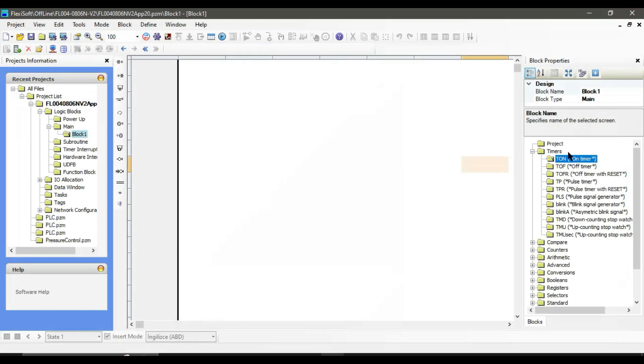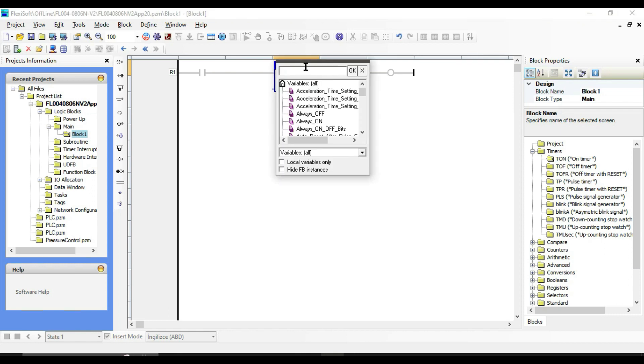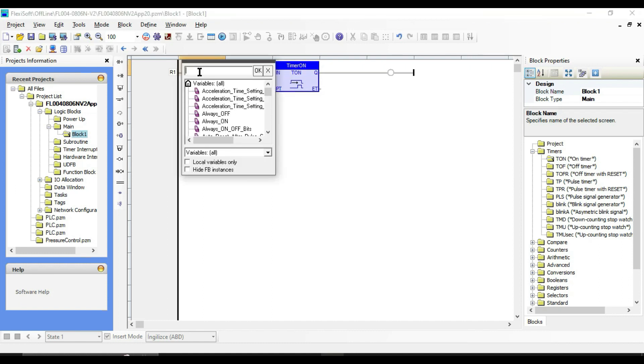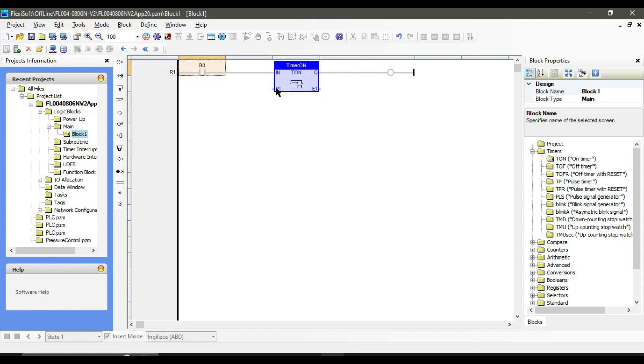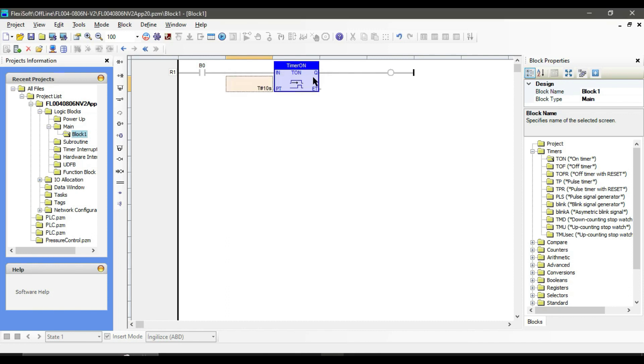Now let's create a simple simulation program to understand better. Give it a name. As you can see, the TON function block has two input pins and two output pins. The input has a boolean data type — I am going to put a simple contact. PT or preset time has a time data type; it is the time that the timer takes before the output turns on. Let's put our delay time as 10 seconds.